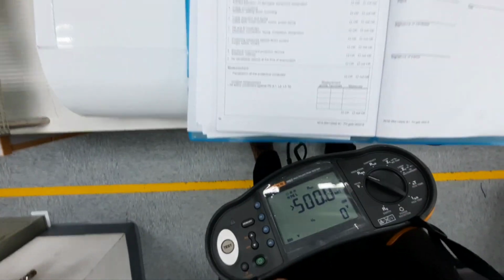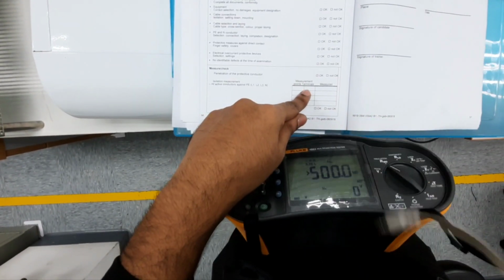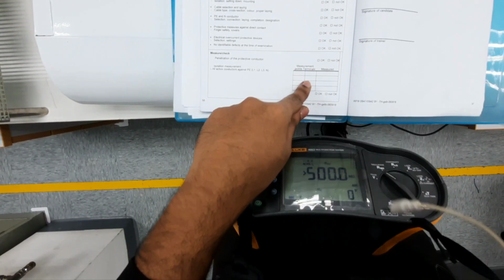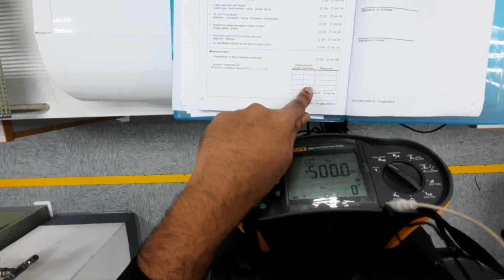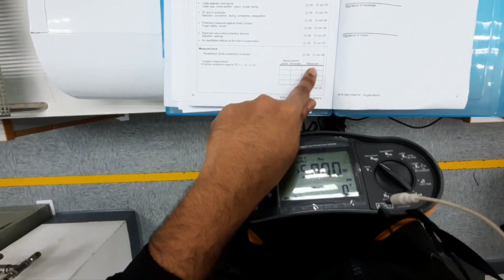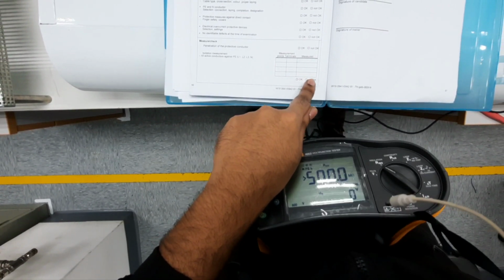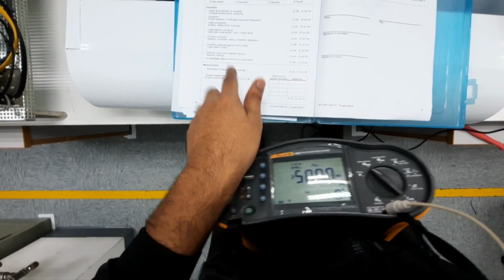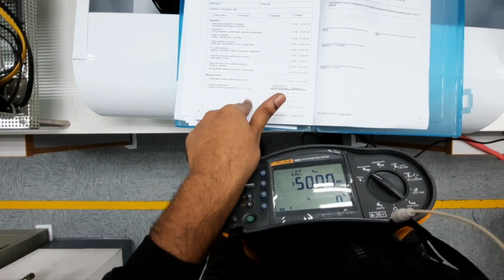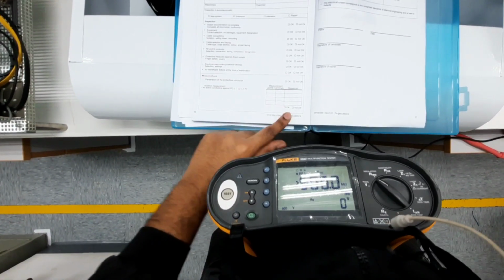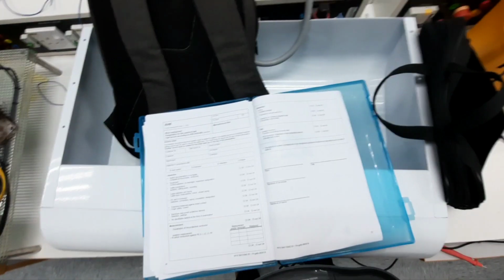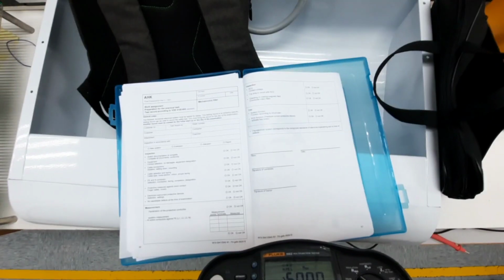So you have done the insulation test. In your staging list you can put all these measurements: line 1 to E, line 2 to E, line 3 to E, and neutral to E. Measure 500 mega ohm, 5 mega ohm, 500 mega ohm - everything okay, since it must be more than 1 mega ohm, which is good. Then you tick it off.